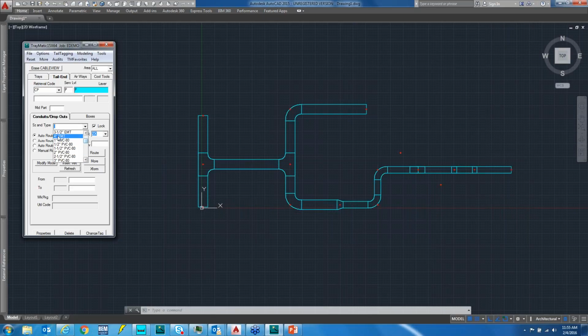We could come up here and say this needs to be a 4-inch EMT or a 2-inch PVC. We could force it to use a specific conduit size and type and lock that size. What I prefer to do is use a generic EMT and unlock the size. This allows the program to route the cables through that raceway and later size the raceway depending on what actually gets routed in it.